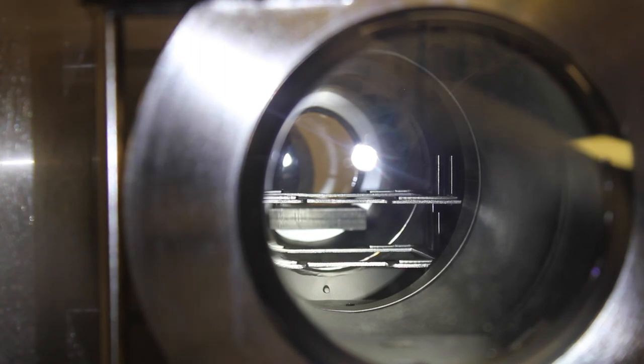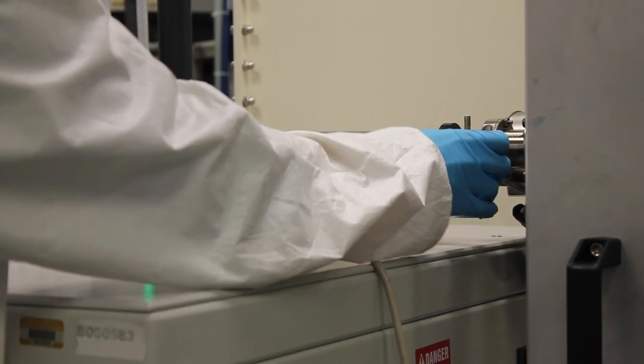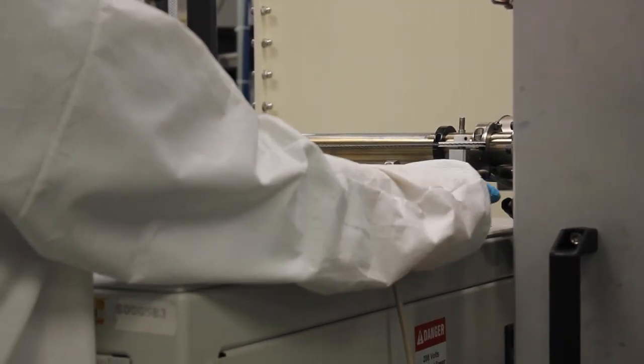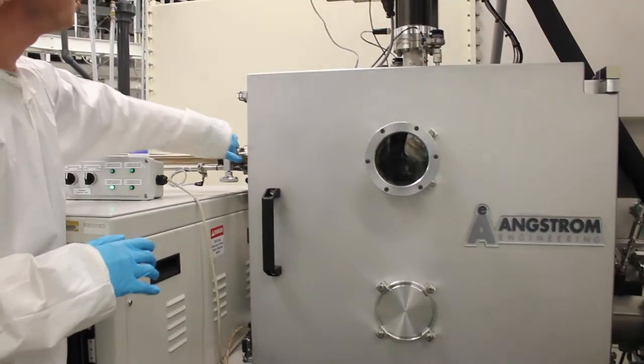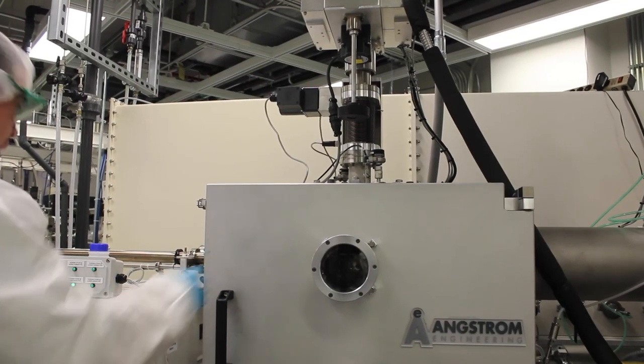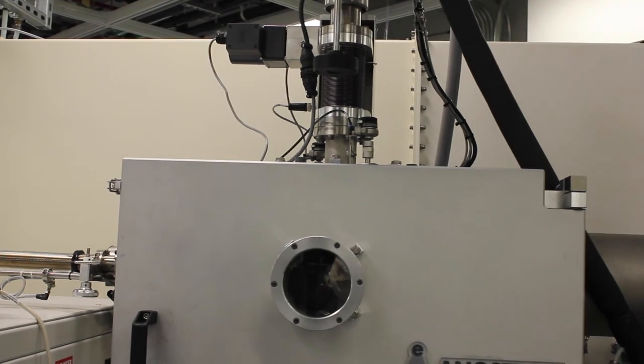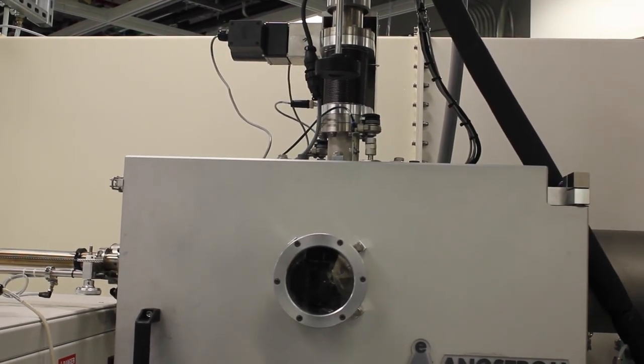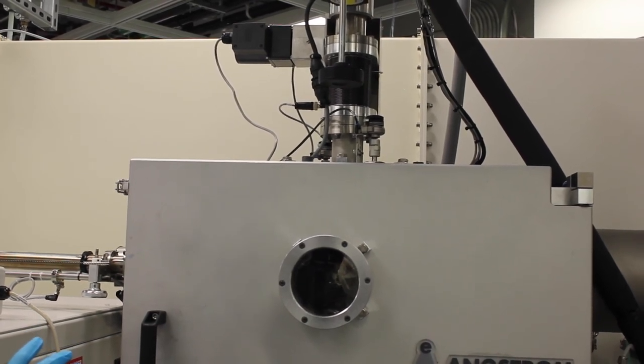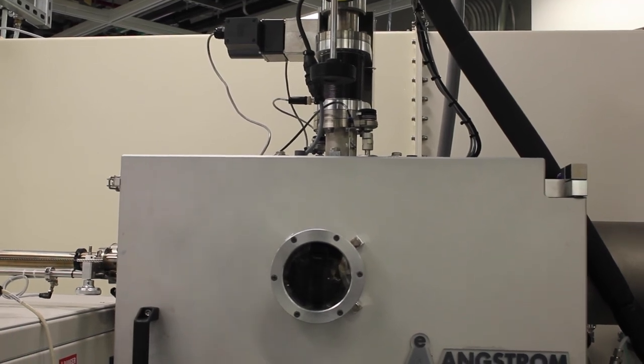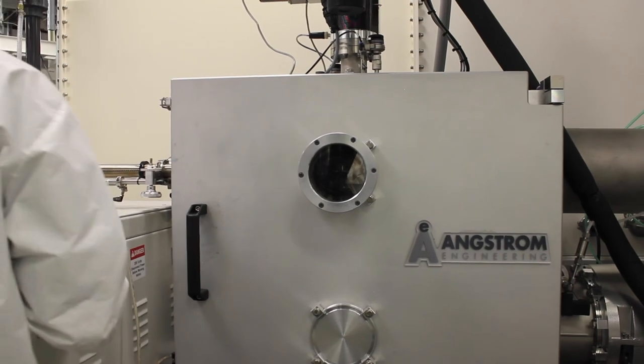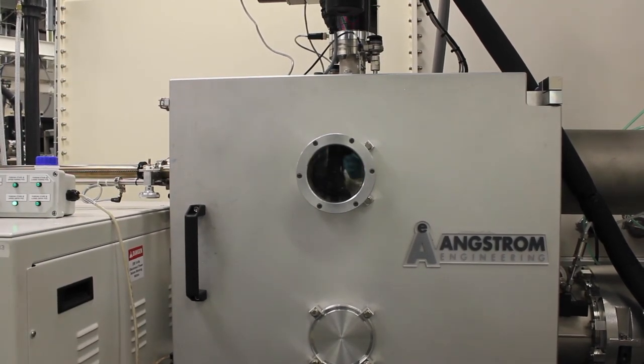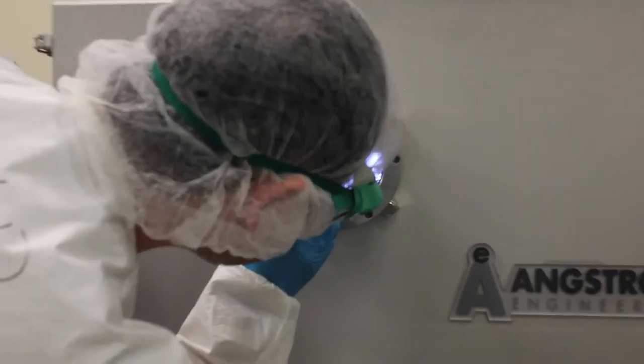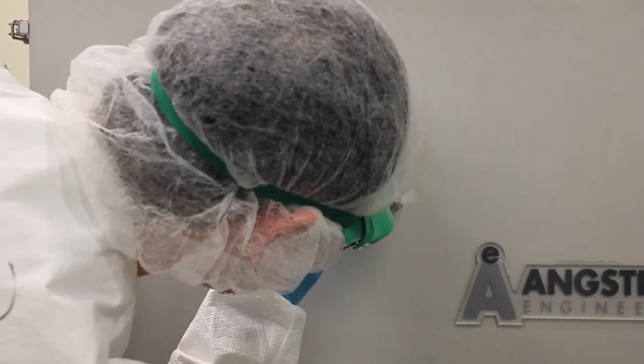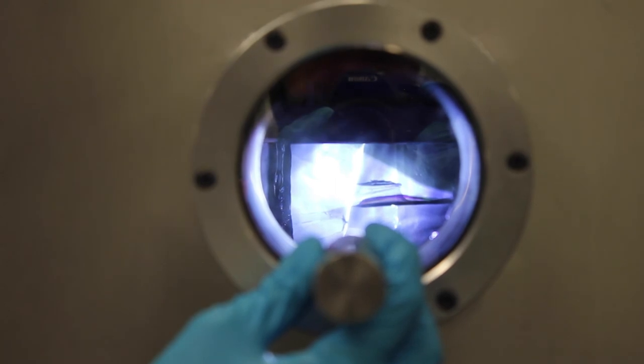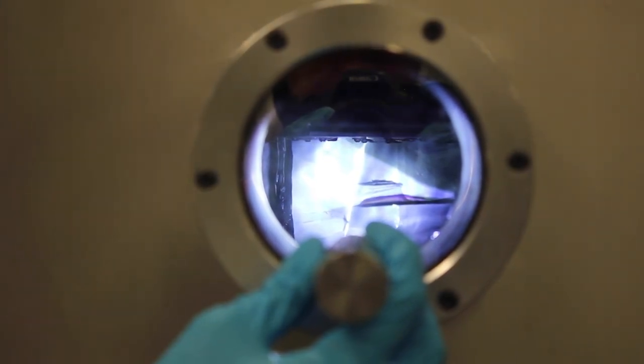Once the puck is manually retracted using this rail system, we can then proceed to lowering the stage holder that's controlled by a motor. And here you can see that the holder is lowering. Once this is lowered, we can push the puck back onto the holder, that's the stage. And this can be further adjusted up and down, depending on the deposition height that you want, or it can be rotated. Shortly you will see rotation, but this was done manually. During operation, we would typically rotate the puck along with the samples in order to provide a uniform surface coating.